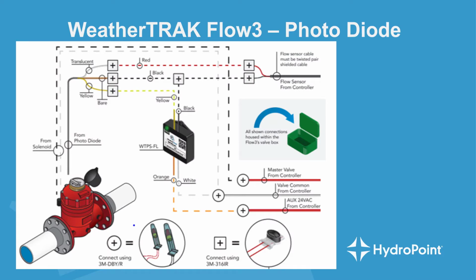Once you've got all the necessary components in the valve box and you're ready to start wiring, get out that wiring diagram and read it very carefully. In my opinion, this is all very straightforward. The trickiest part is that there are two connections on the wiring diagram that will require three wires in one connection. We'll start with those.